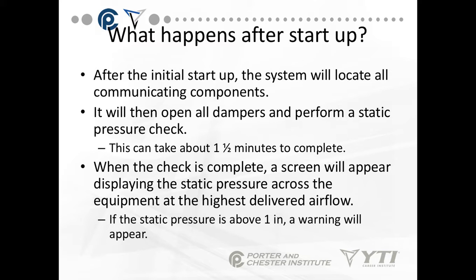After the initial startup, the system will locate all communicating components, then open all dampers and perform a static pressure check. This check takes about one and a half minutes to complete. When complete, a screen will display the static pressures across the equipment at the highest delivered airflow. If the static pressure is above one inch water column, a warning will appear, because in normal systems we do not want static pressures above one inch water column.